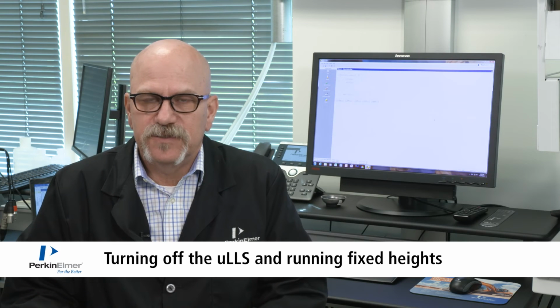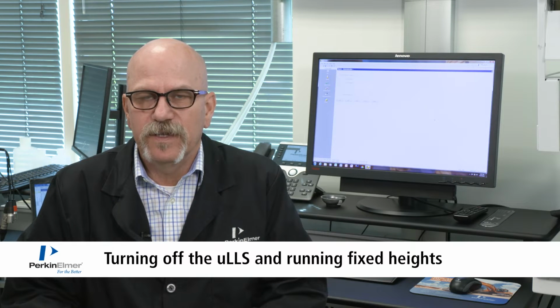With the uLLS instrument, some of them come with a uLLS or ultrasonic level sensing option. Sometimes if you ever experience problems with your ultrasonic level sensing, it may become necessary to bypass that or turn that option off for a short time until your service person can come in to repair the issue if one of the sensors were to go out or something like that.